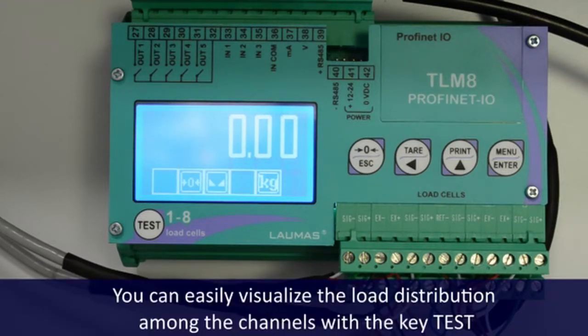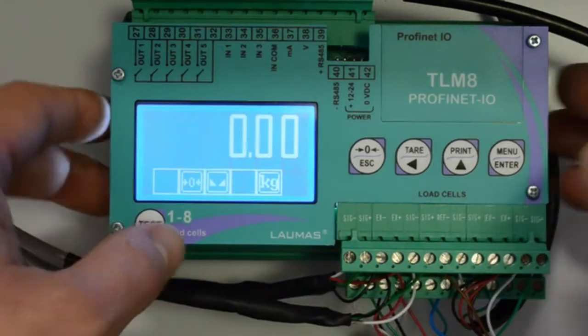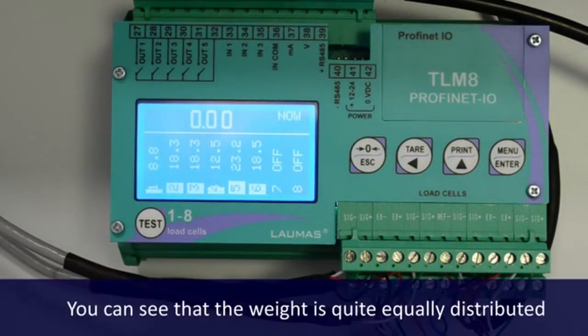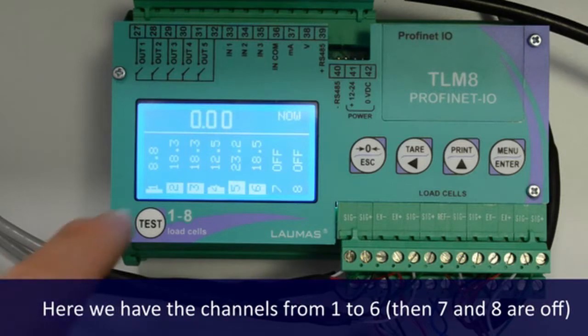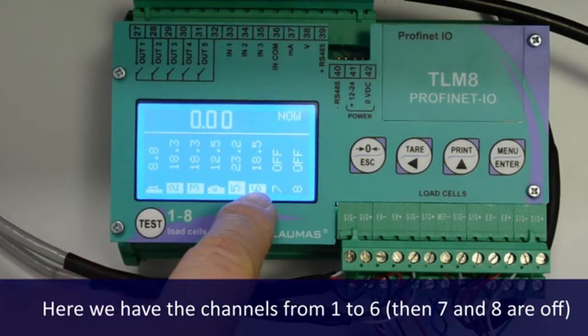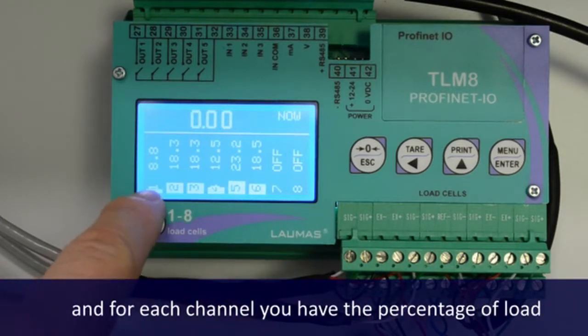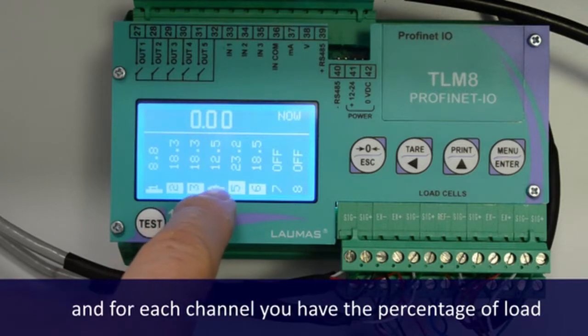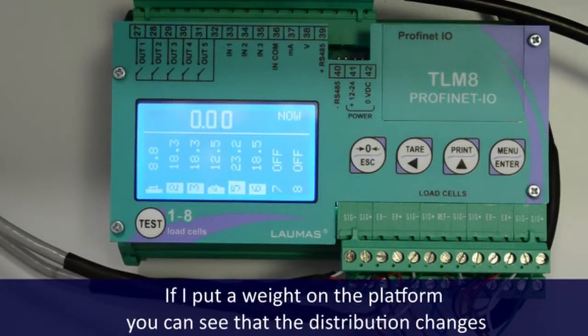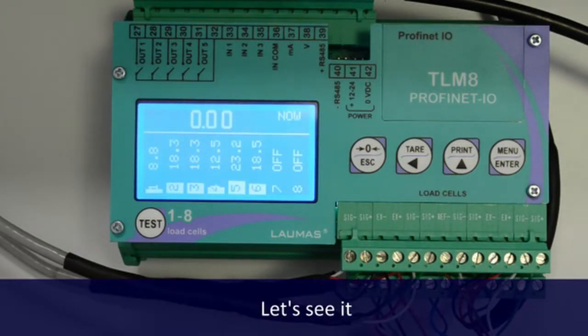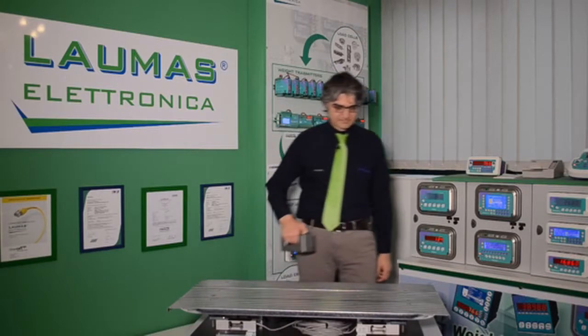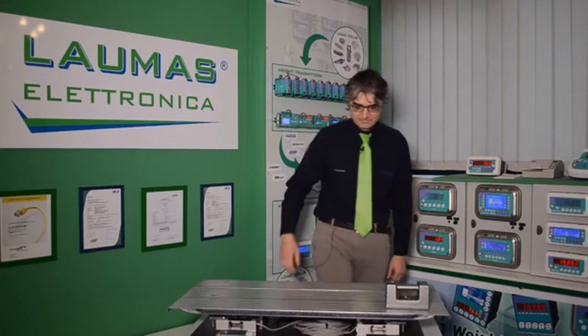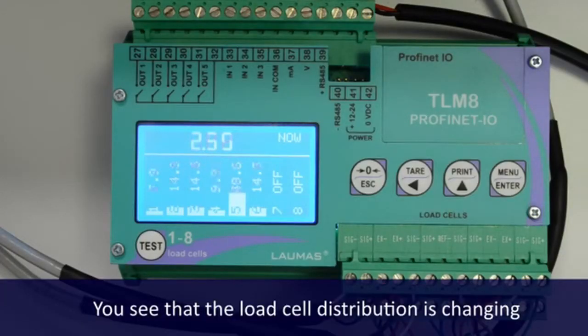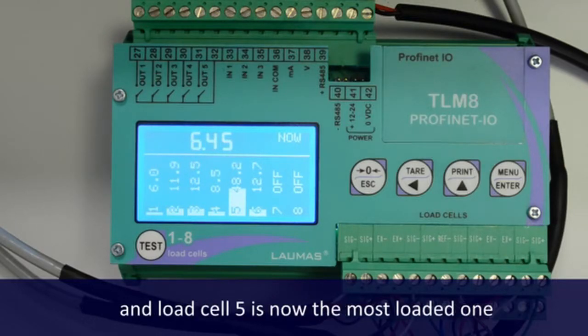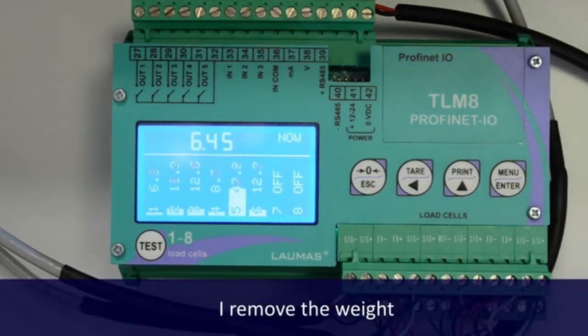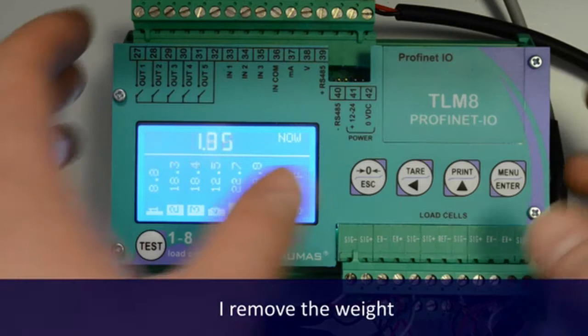You can easily visualize the load distribution among the channels with the key test. You can see that the weight is quite equally distributed. Here you have the channels from 1 to 6, then 7 and 8 are off, and for each channel you have the percentage of load. If I put a weight on the platform, you can see that the distribution changes. Let's see it. You see that the load cell distribution is changing, and load cell 5 is now the most loaded one. Okay, I remove the weight and go back to zero.